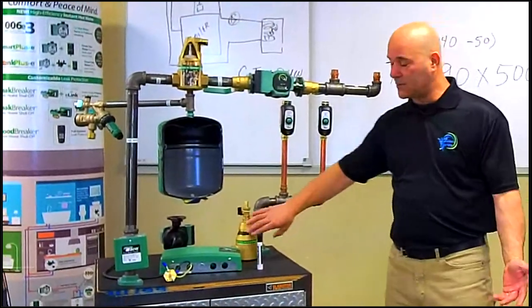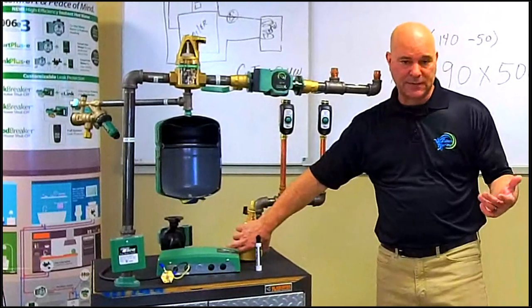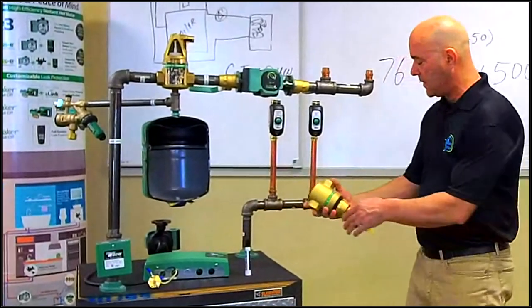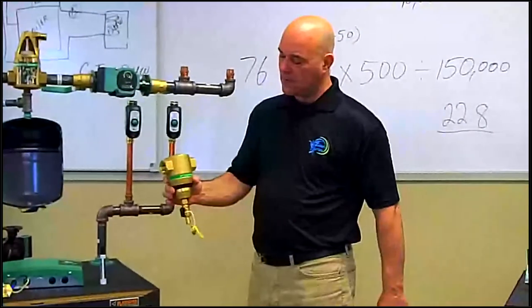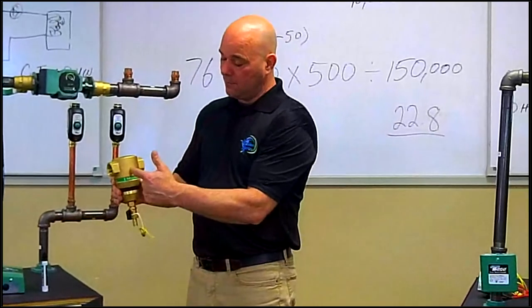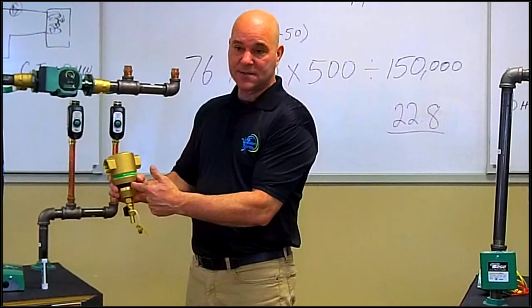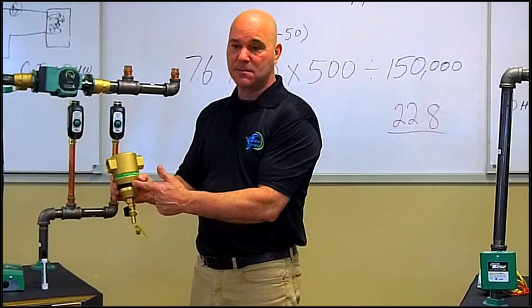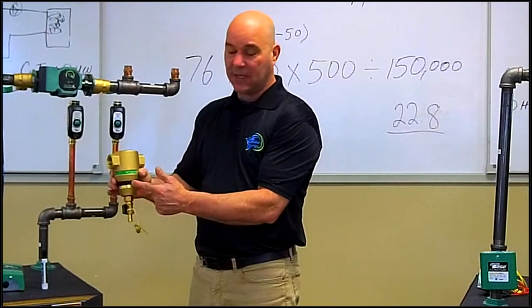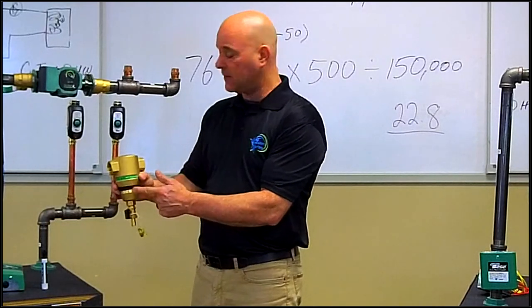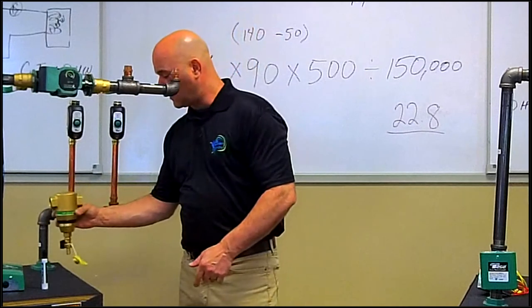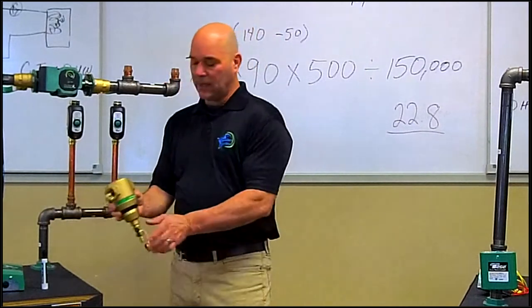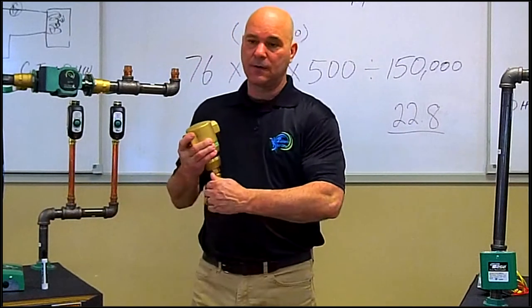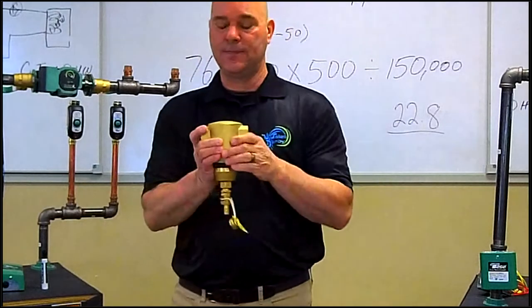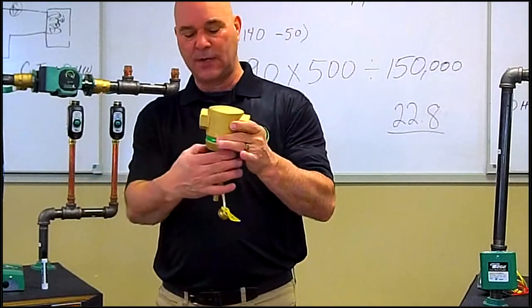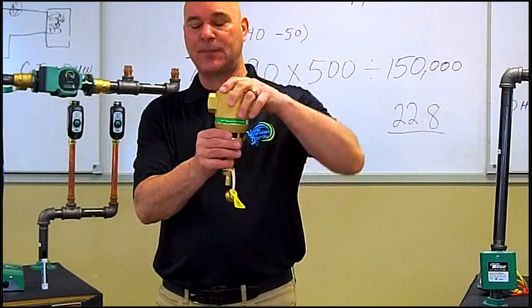All right, and just while we were talking earlier, I should have talked about this a little earlier, but it's right here in front of me. This is a Taco, it's a 4900, basically, that Taco has put a 13,000 Gauss magnet. So this becomes a mag dirt separator. So this would be mounted right here on the boiler. And there's a valve that comes with it. There's a cap that comes with that if you want to use it. This is your magnet strip right here.